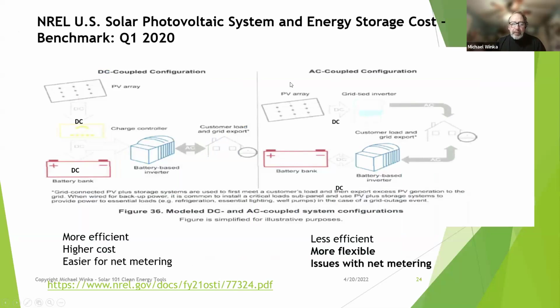Here's a term to get familiar with: how you connect batteries, either AC coupled or DC coupled configuration. If you have an existing solar system, you're typically going to do an AC couple, where your system on the roof generates DC power, goes into an inverter, you use it, and it goes out onto the line. You can take power off the line and it goes to another inverter that inverts it back to DC for the battery. Typically you're doing that because you already have a string inverter, so if you're retrofitting the system, you have to add these two components, another inverter. Once you do that, you're losing some energy — just like your phone or laptop charger, you feel that heat — that inverter loses some energy, so it's less efficient but more flexible, giving you more options in this configuration. You also have some issues with net metering, and you may want to talk to the utility about how you set it up — they may require a relay so you're not net metering power from the grid.